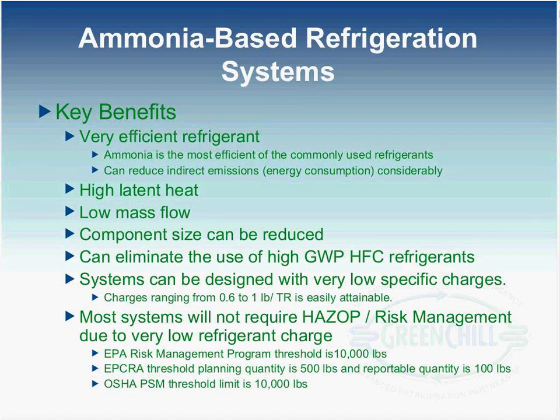Ammonia, as you all know, has been used for hundreds of years, and it's an excellent refrigerant from a thermodynamic point of view. The key benefits you would see is it is a very efficient refrigerant, and you can see energy efficiency gains when you compare with HFC refrigerant anywhere between 5 to 10% depending on what refrigerant you are comparing to. This would reduce your substantial indirect emissions. Like for like, you would see about 15% reduction in LCCP or TEWI. And when you compare with a conventional system, you would see about 50 to 65% reduction. This directly fits into the GreenChill mission of using environmentally friendly refrigerant.